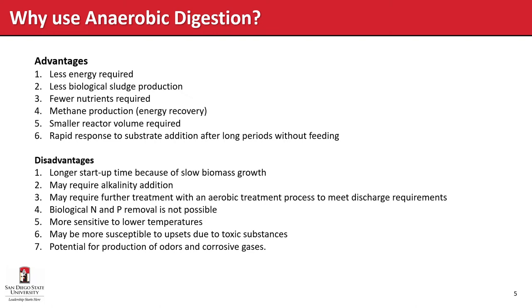Effluent typically cannot meet discharge requirements directly, so further treatment after the anaerobic process is often required. The process is sensitive to low temperatures, which can be an issue in colder climates, and is susceptible to upsets due to toxic substances. There is also potential for production of odors and corrosive gases, most commonly hydrogen sulfide, because all sulfur in the substrate becomes reduced — sulfate going in will be reduced to hydrogen sulfide.